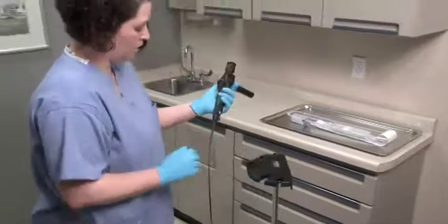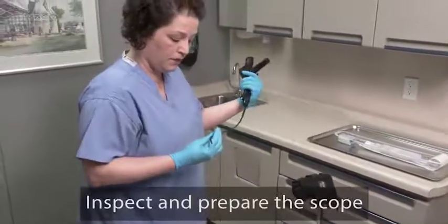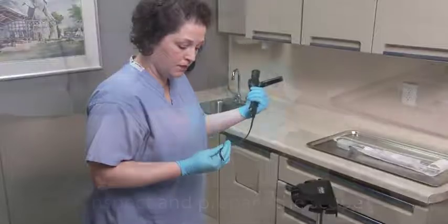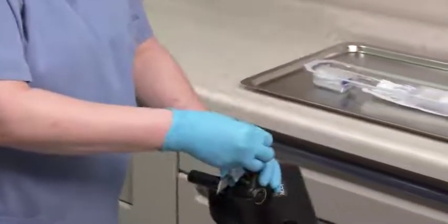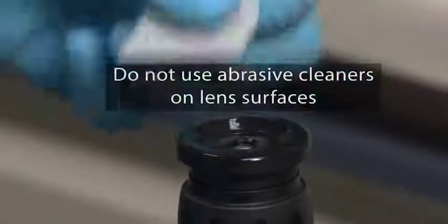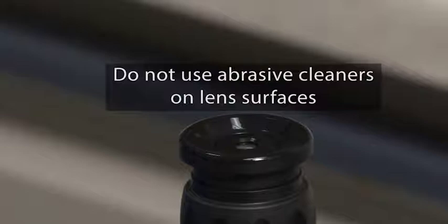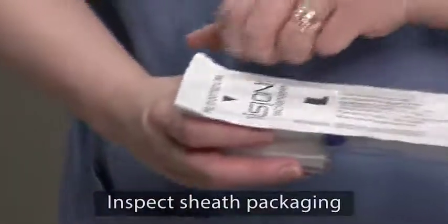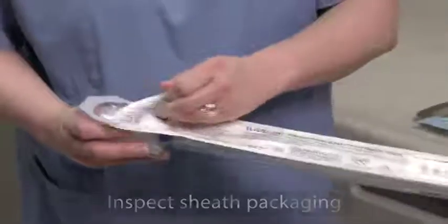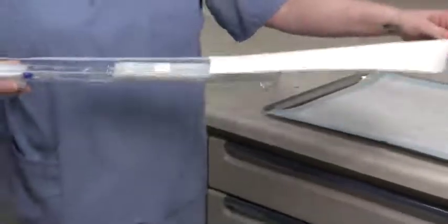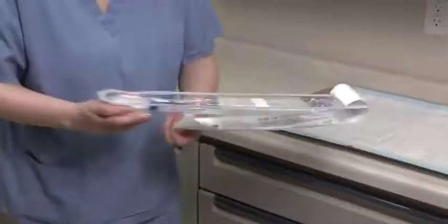Before installing the sheath, check the cystoscope insertion tube for any defects or damage. Clean the eyepiece and lenses on the distal tip of the cystoscope with an alcohol prep pad. Verify the focus and clarity of the image. Do not use abrasive cleaners on the lens surfaces. Check the EndoSheath disposable package for defects or damage. Open the outer packaging for the sterile sheath. Open the sheath's package carefully.